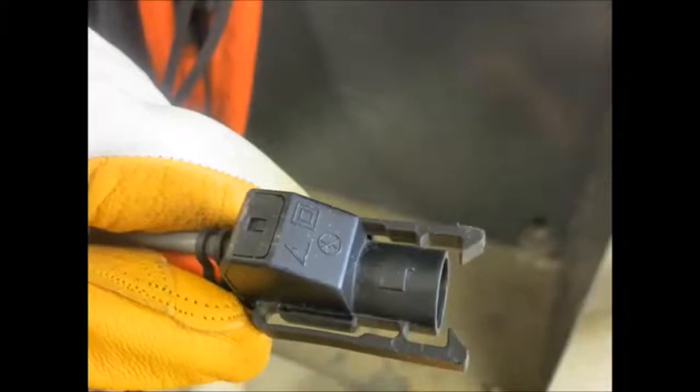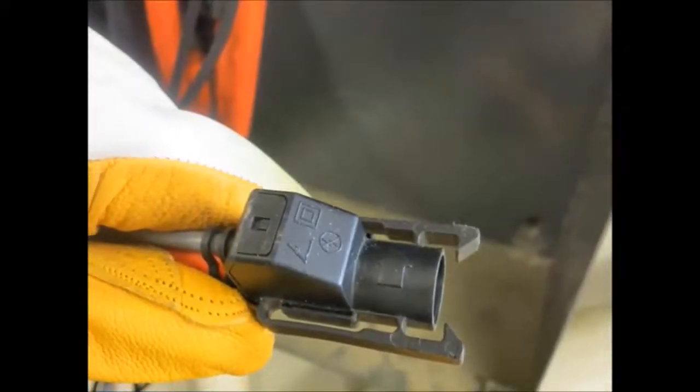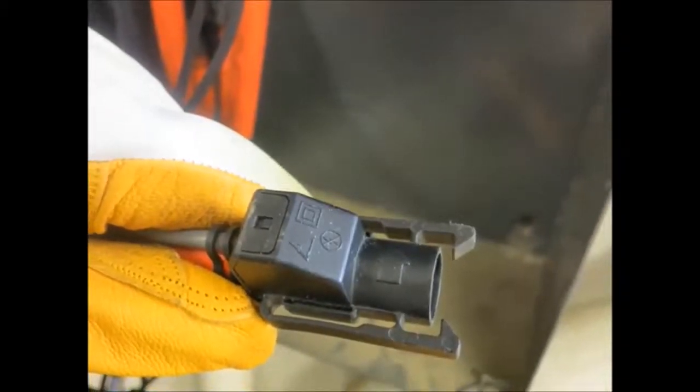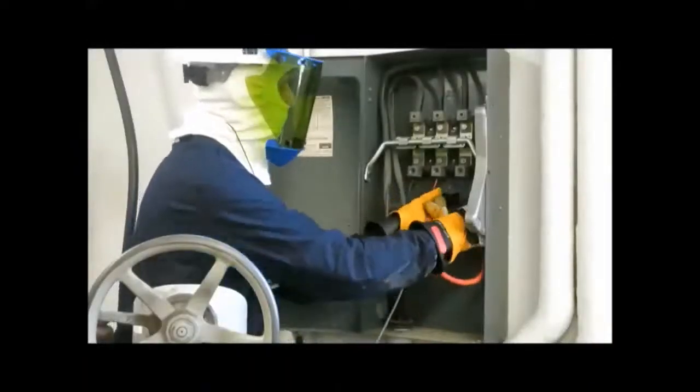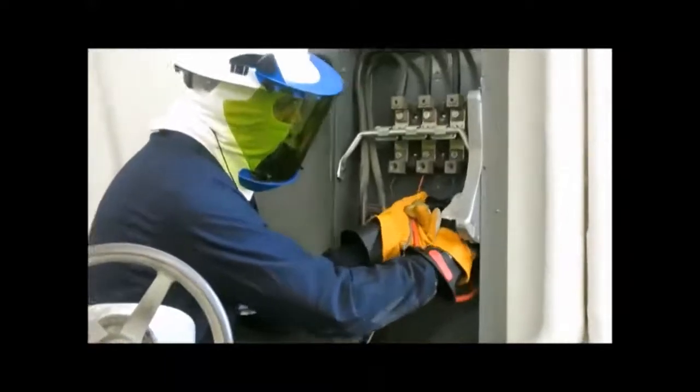First, ensure that the arrows on the current sensor transducers are all pointed in the direction of the current flow. Place one transducer on each leg of the three phases. The neutral current transducer should be placed around a ground wire.